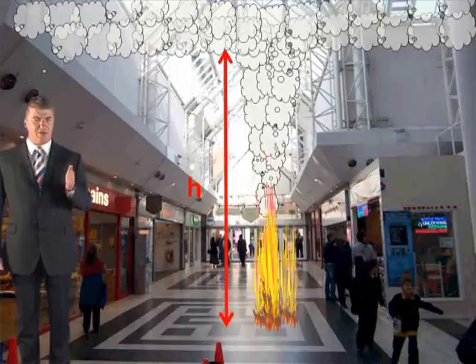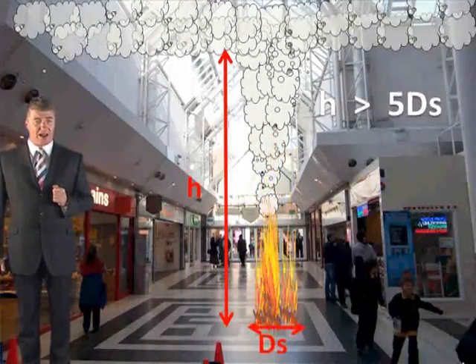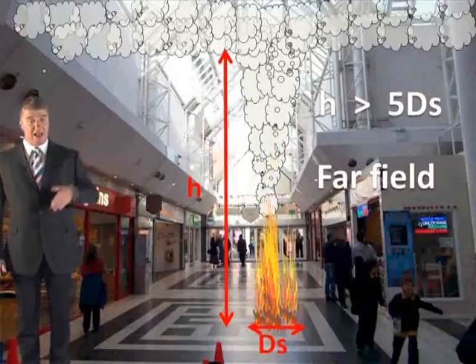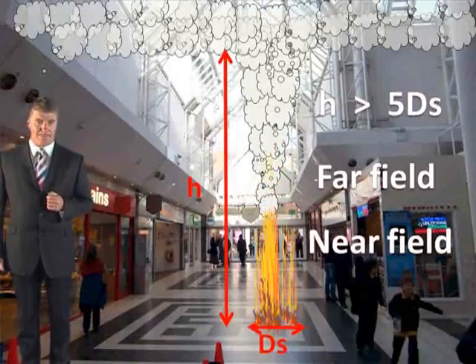Now, first of all, we know it's an axisymmetric plume, but not whether it's a near field or a far field model. And this is the first thing you need to do. The rule is that if the clear layer height is greater than the longest dimension of the source times 5, then it's a far field model. If not, it's a near field model.